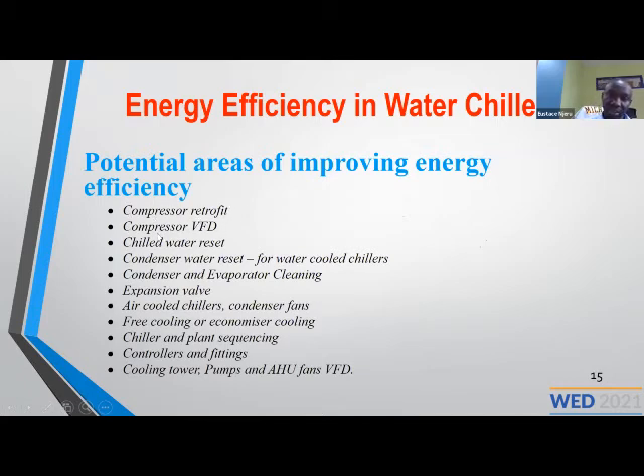The other area of energy efficiency: you can use a VSD, depending on how your cooling load is varying. In most cases, temperatures, like in the tropics, vary from morning to evening and at night. So you need to know when you are operating your system and see the varying load, and use your controls in conjunction with a VFD on the compressor, so that when the load is not very high, you can run at lower speeds, or run a smaller compressor, or run one compressor if the water chiller has multiple compressors. So a VSD will be able to reduce the speed. And you must be very careful when using a VFD, because it is almost inefficient if you reduce the speed of a motor to less than 20% of the original speed. So you need to operate within that 20%.